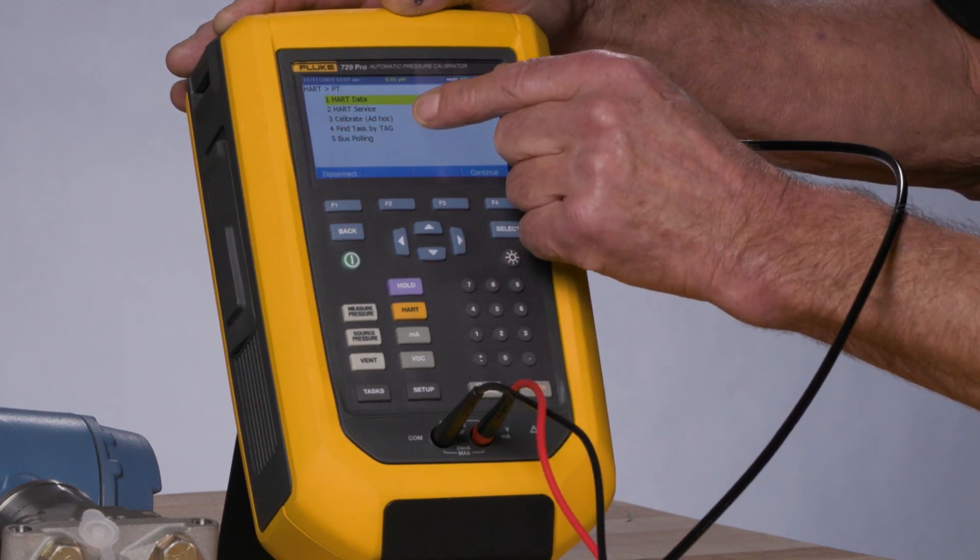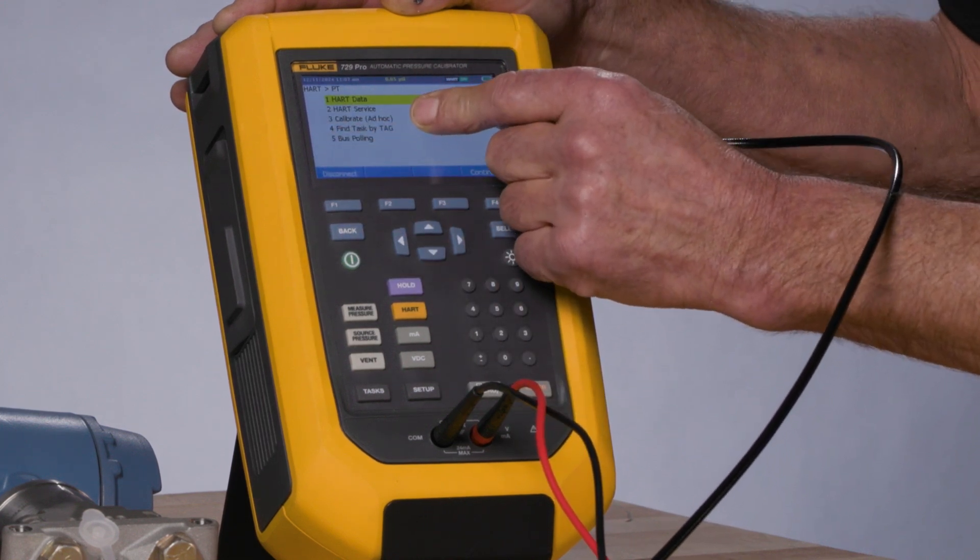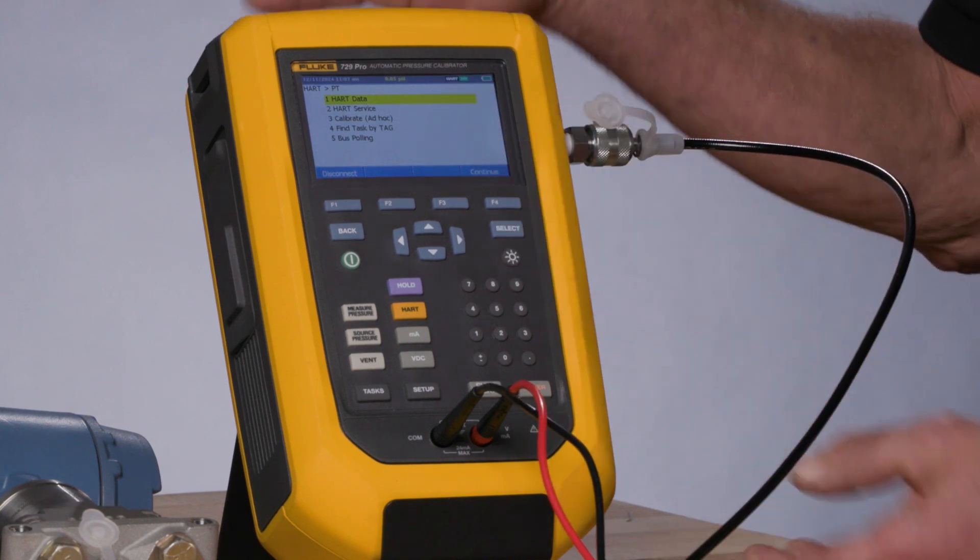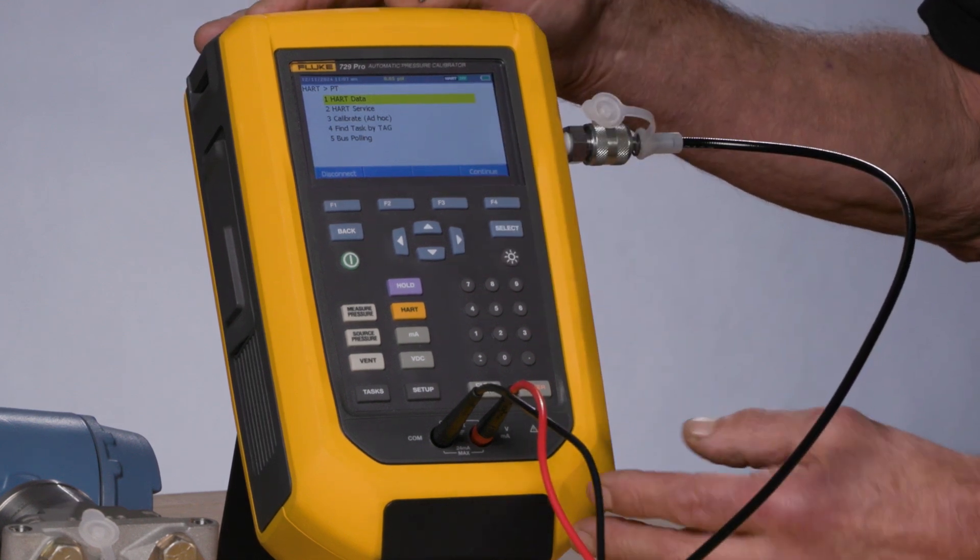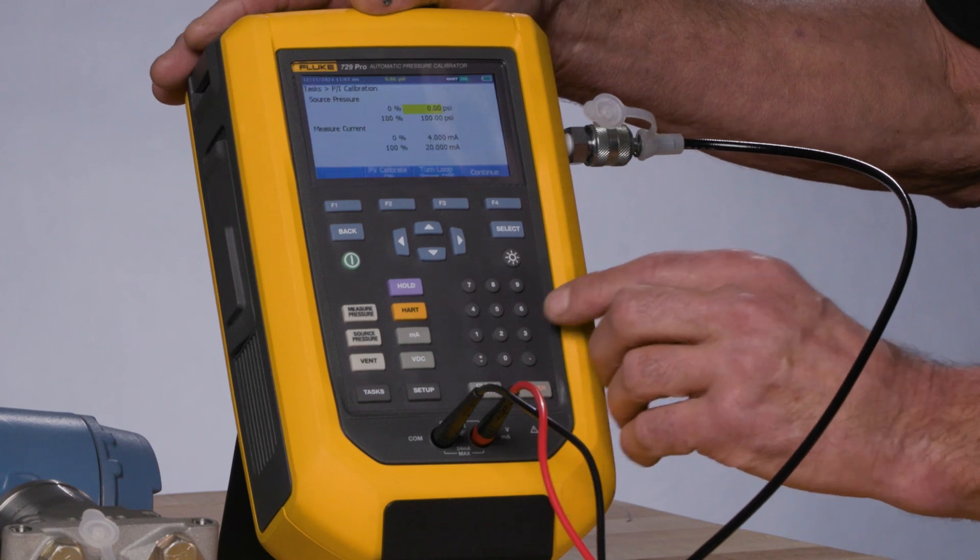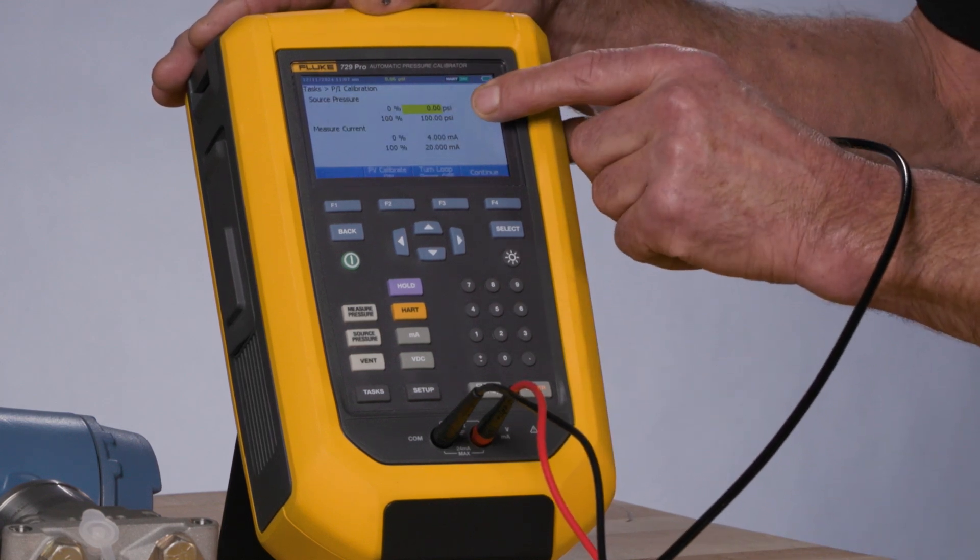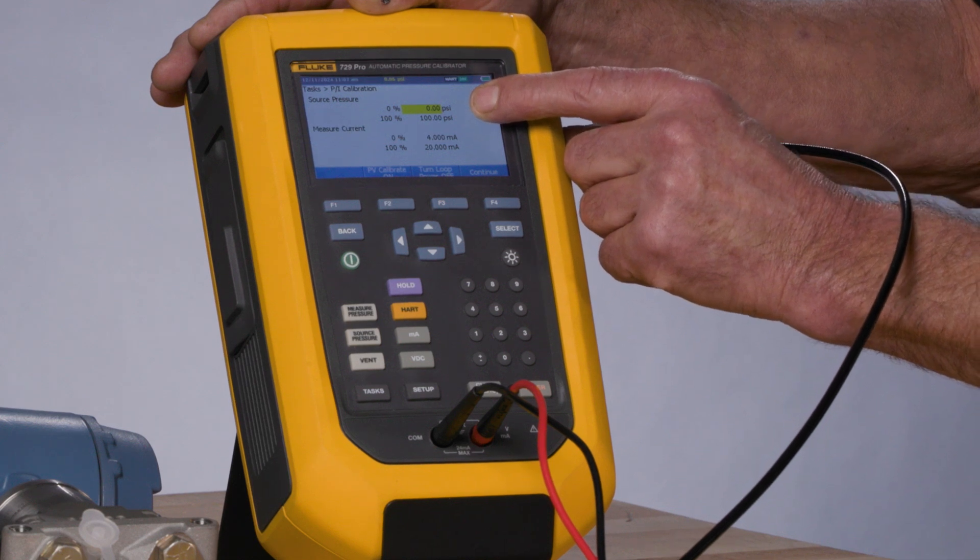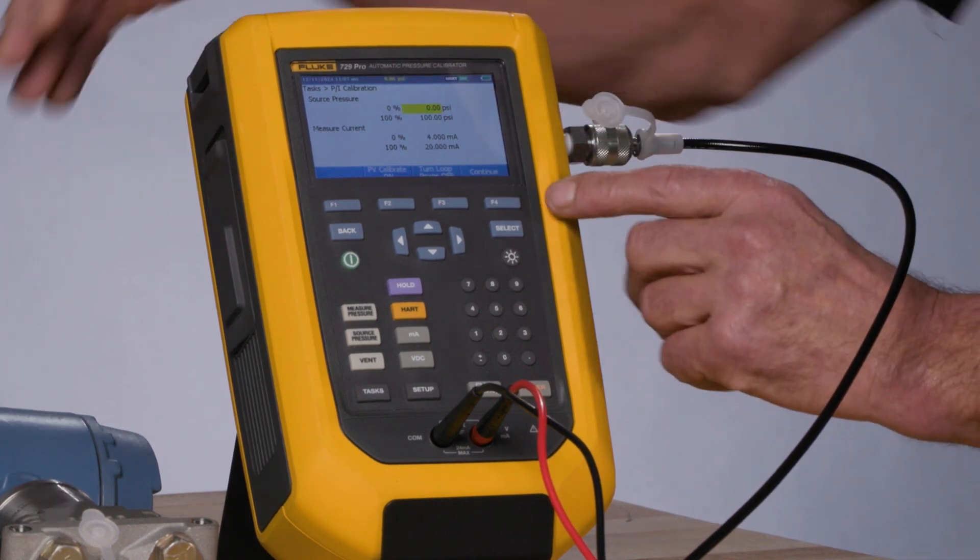Select back, and now the next option, calibrate ad hoc. We'll use that device configuration to pre-configure the calibrator for the calibration test. So I select 3, and I notice it's automatically set up to calibrate 0 to 100 psi based on the HART configuration of this particular device.